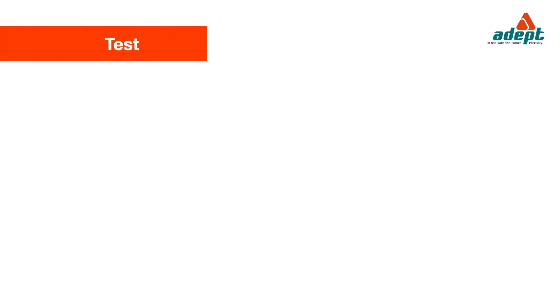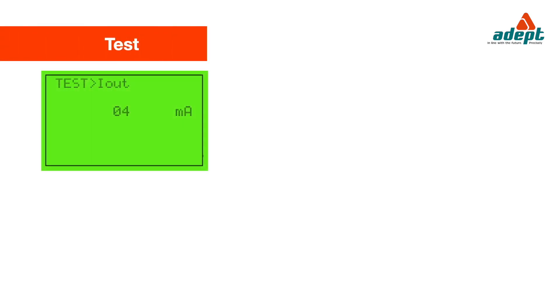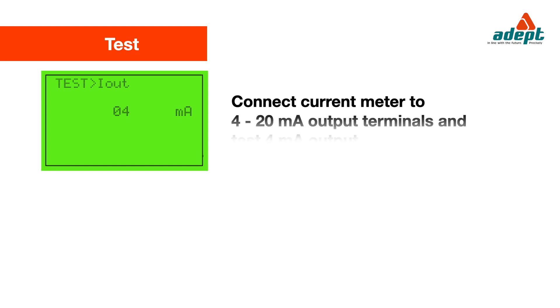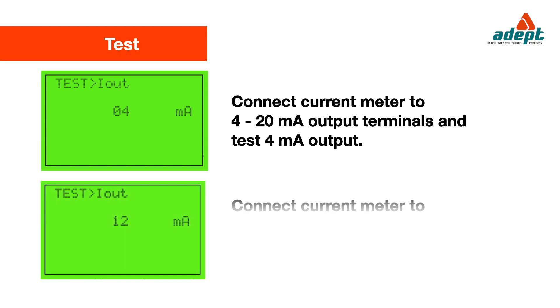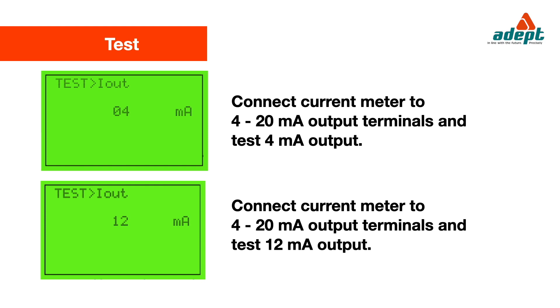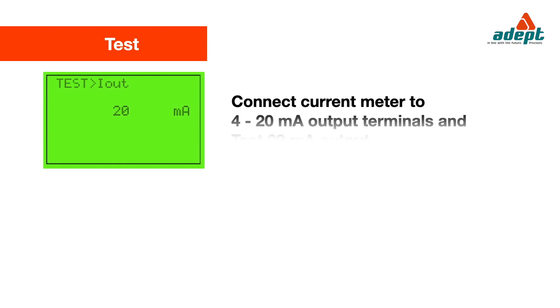Test: Connect a current meter to the 4 to 20 mA output terminals and test the 4 mA output. Connect a current meter to the 4 to 20 mA output terminals and test the 12 mA output. Connect a current meter to the 4 to 20 mA output terminals and test the 20 mA output.